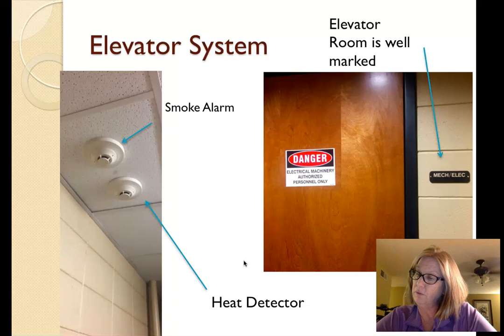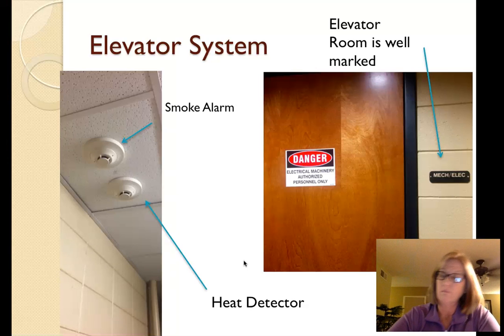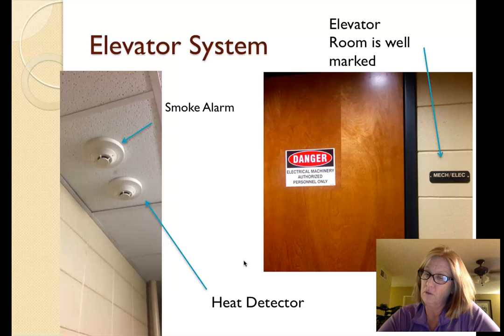NFPA 72 requires smoke and heat detectors in the same locations. These devices were about 2 feet apart from each other. That's the most that they can be. You can see that these two smoke alarms and heat detectors are very close together.